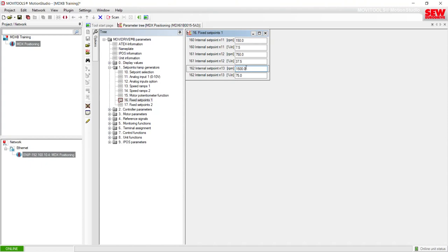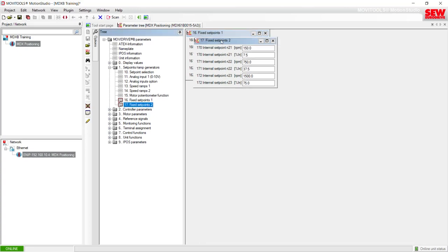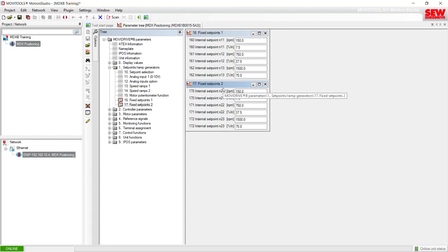There are three different set point speeds that can be set for this MOVIDRIVE. When you see Speed Ramps 1, Speed Ramps 2, Fixed Set Points 1, Fixed Set Points 2 — the number two means it is the second parameter set. Currently we are only using the first parameter set, so don't get confused by Fixed Set Points 1 and Fixed Set Points 2, because Fixed Set Points 2 is only valid when using parameter set number two. Otherwise leave these to the default setting since they're not being used.